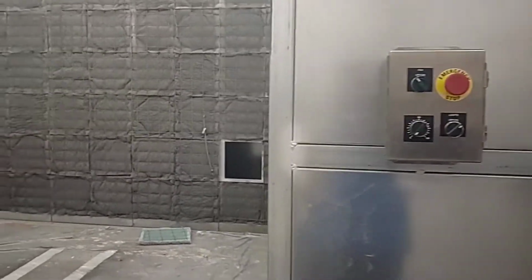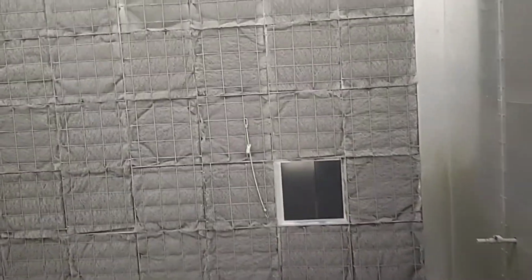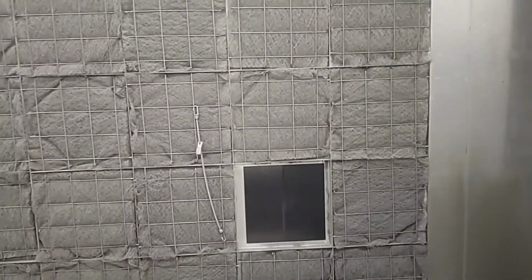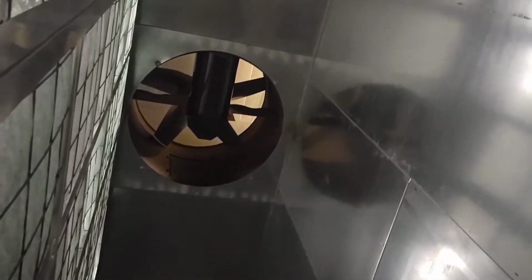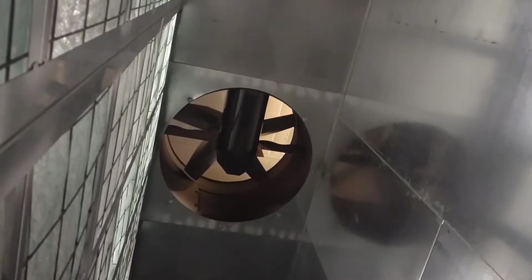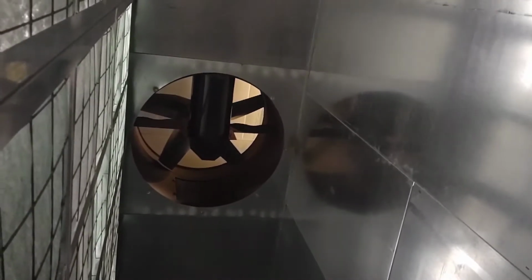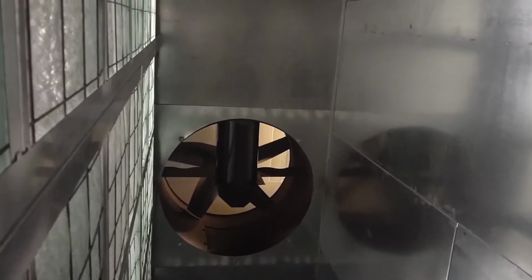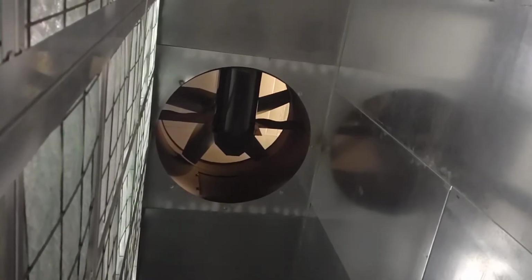And one more thing I wanted to make sure and program for was actually to apply DC braking before the fan begins to spin. The reason I wanted to do that is just in case that big fan blade starts to free spool because of air differential in the building, we want to stop it before we start spinning it the other direction. So I've actually started some of the fans in the building right now, to see if I couldn't make it do that, but it's not, and that's probably a good thing.